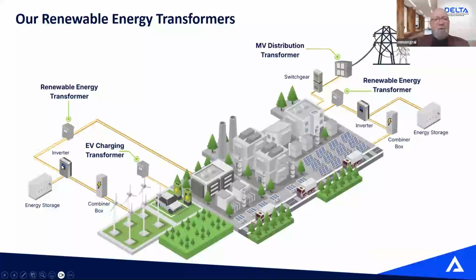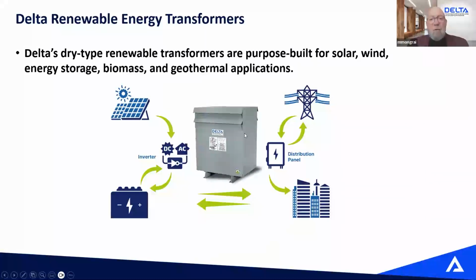So that bidirectional duty, if I could say, is quite important in those transformers, because the typical transformer installed in an electrical room feeding a panel will be fed by the grid at 600 and will feed a panel. So it's upstream, downstream. In the case of renewable energy, the energy will flow from either the building, inverter, or battery. So the transformer is like an energy router, if I could say, in those cases. The transformer will be sitting at the center of your system: inverter, battery, solar panel, wind farm. You have your grid, you have your panel, you have your building.